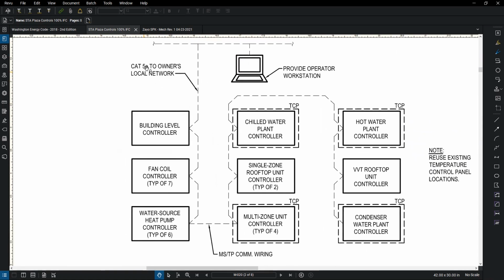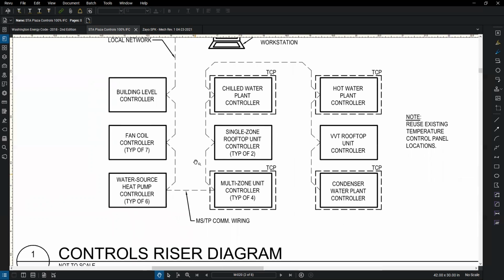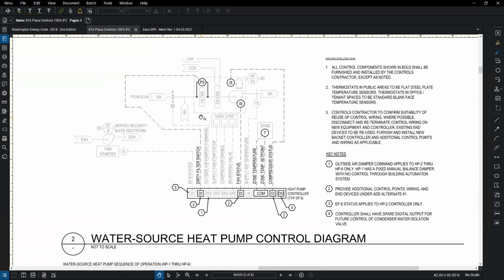So all of this gets connected by a Cat5 cable to get to the owner's network. You have a building level controller that is essentially the brains of the entire operation. And then you have your individual unit controllers. So we have 7 of these units. We have 6 water source heat pumps. We have 4 big multi-zone units. And it just kind of gives a representation of the hierarchy of everything on the project and everything that the control system has to pick up. And then you get into the specific equipment.